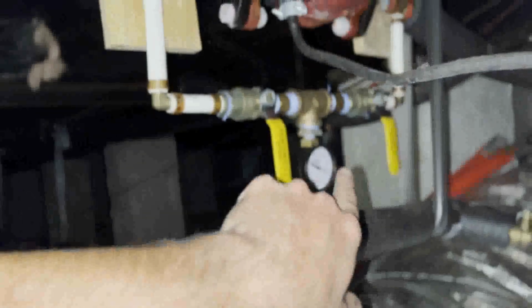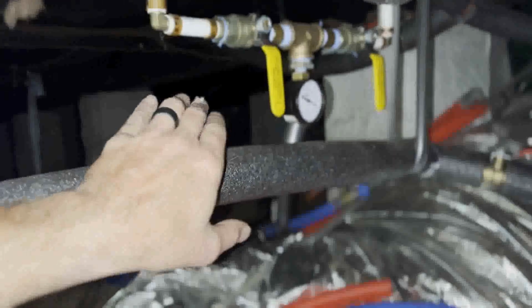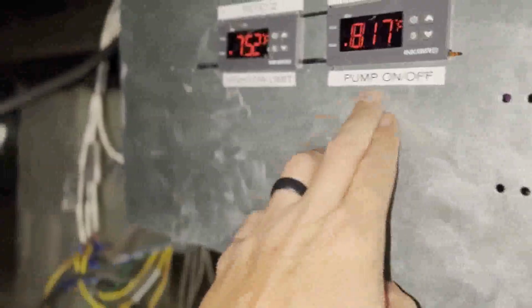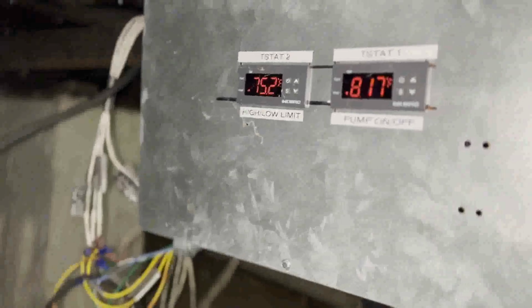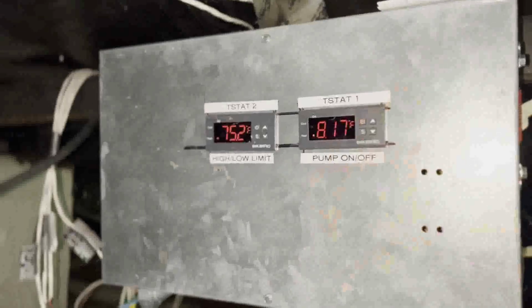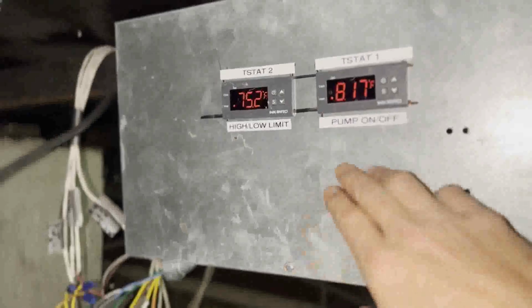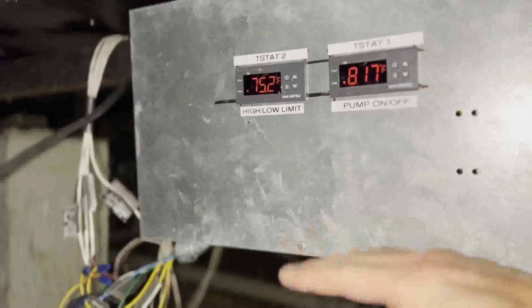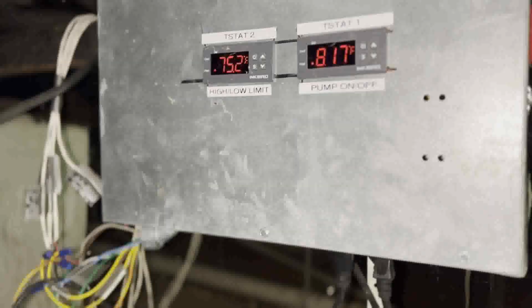Basically, same thing here. This is just a gauge array so that you can open, verify pressure, close, open, verify suction pressure, get a head, pump curve, look up and see what that pump is moving. Basically, how this works is this thermostat, when the water gets hot enough to a preset amount, it's gonna bring on the pump. That's all this one's gonna do. When it gets so cold, it's gonna shut the pump off.